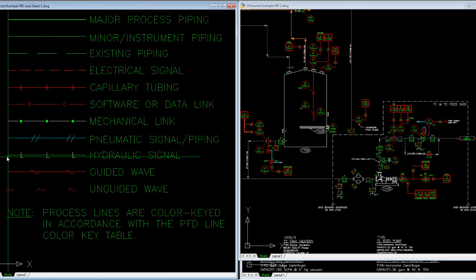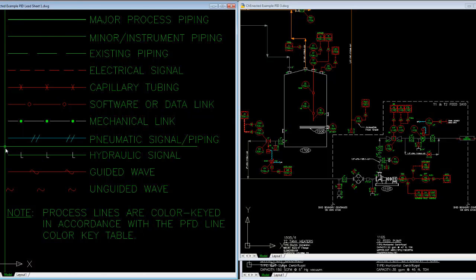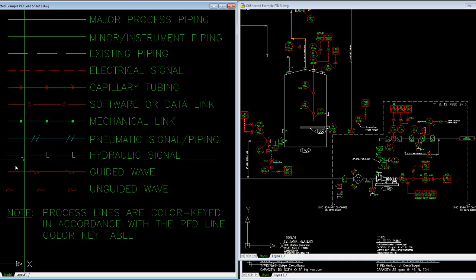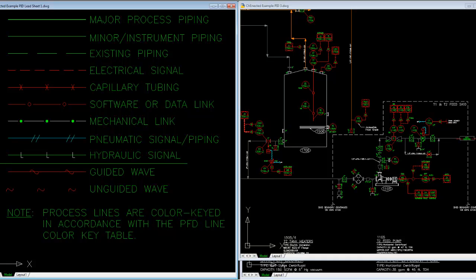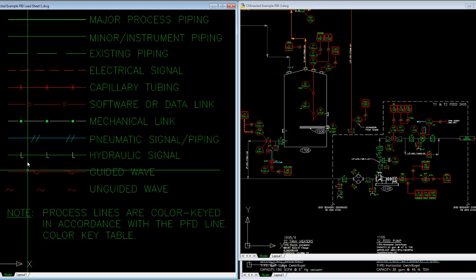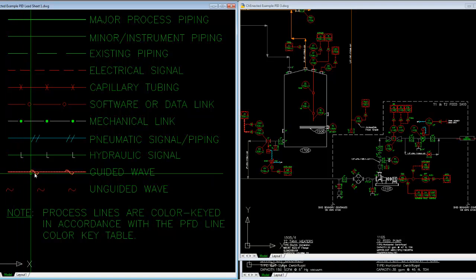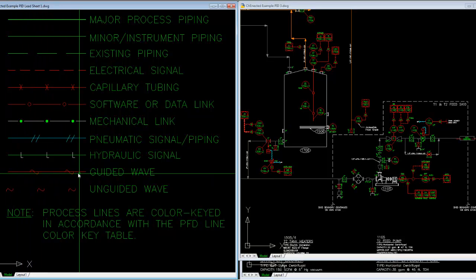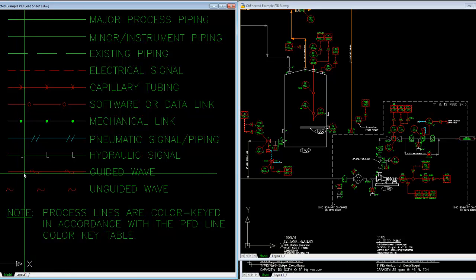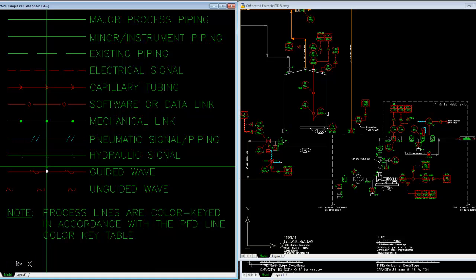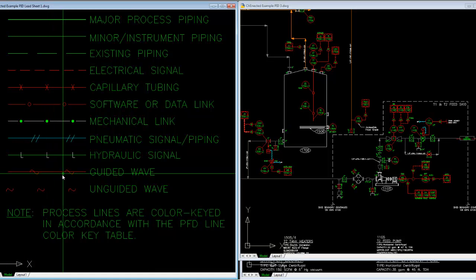You can have hydraulic signals similar to instrumentation. Then the last two are very commonly used to illustrate mostly level or distance type instrumentation. In the case of a guided wave radar level element, you may show that that level instrument is working with a principle of sending guided radar waves down a line. And they're guided in that they run around that antenna, which is physically dropped into the vessel.